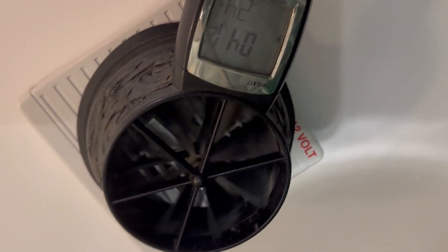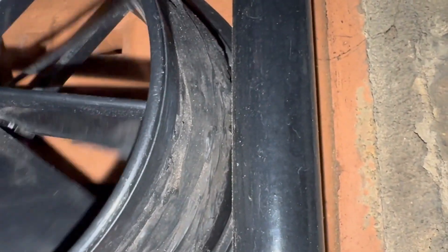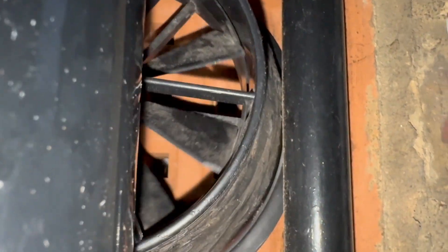The extractor fan is hardly working at all. The extractor fan has been switched on and there's nothing — no flow. Checking with my finger, that's what should be happening, but basically zero flow. It's not going through — it's going into the ceiling void, I think.